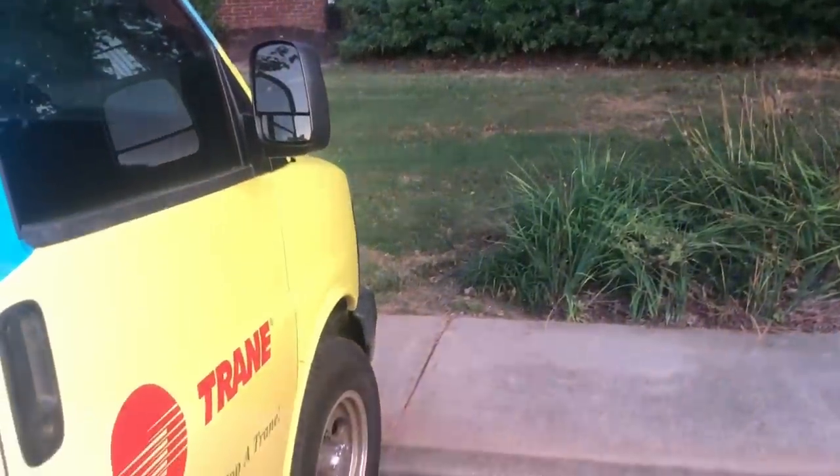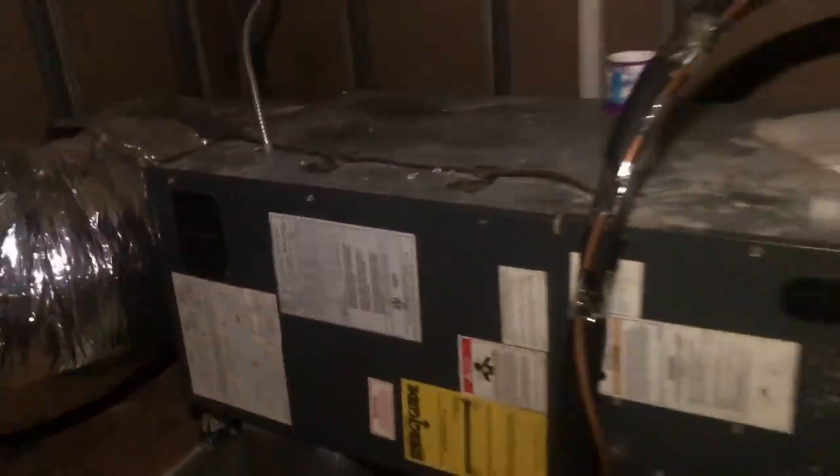There's four right here that don't go to these four — it really doesn't make much sense. Anyway, I'm going to suspect the drain pan is full, so we're going to get up in there and look. Of course, no ladder, just a hatch, so it's ridiculous to get up here. And they put a water heater tank in the attic — that's crazy. Big old drain pan slam full of water. Probably clogged up. I couldn't find anything outside where it goes.